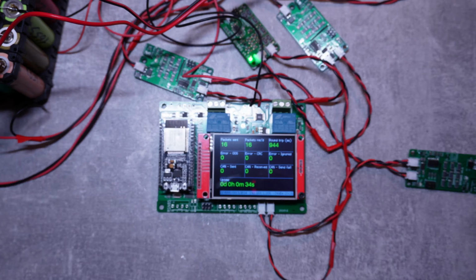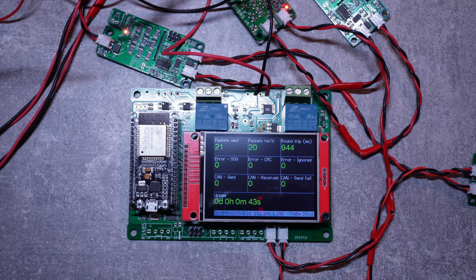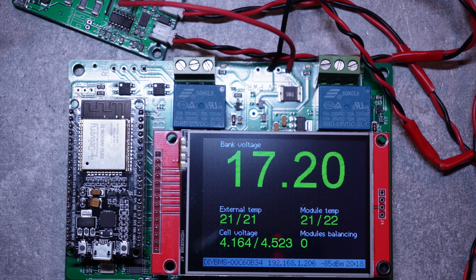If I now turn the charger on, you can see the red LEDs on the modules come on, meaning some of the modules are beginning to balance. It still says module balancing 0, and now we have 3 modules that are balancing. Excellent, so now we have the display as well, so this can be easily monitored without the computer.